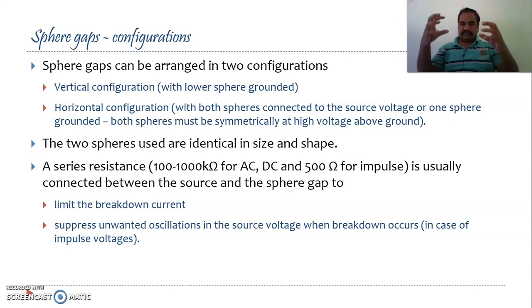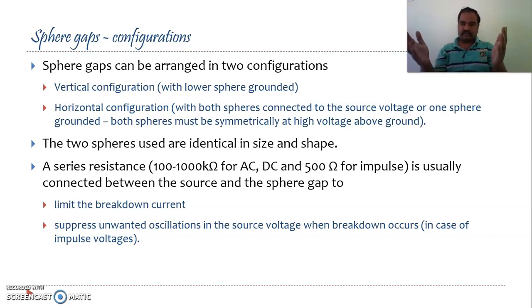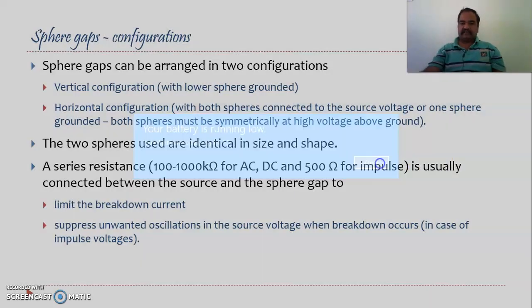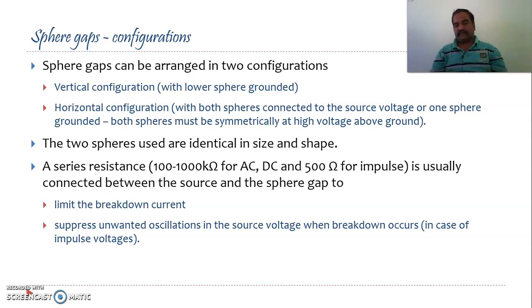The two spheres must be identical in size and shape. Whenever you are applying voltage, to protect the arrangement you use a protective or series resistance. Its value will be somewhere around 100 to 1000 kilo-ohms for AC/DC, and somewhere around 500 ohms for impulse voltage in practice. This resistance is used between the source and the sphere gap to limit the breakdown current — because if spark-over happens immediately the current will be very high — and also to suppress any unwanted oscillations in the source voltage when breakdown occurs.